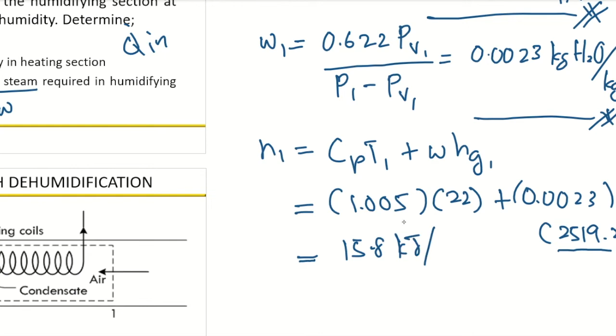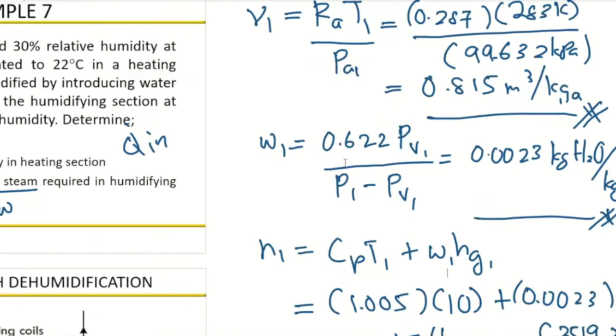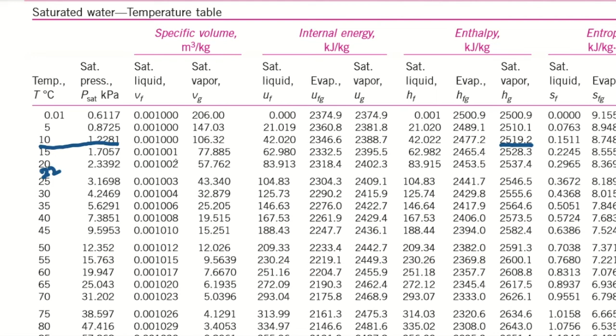So next we determine h2, which is Cp T2 plus omega 2 Hg2. Cp is 1.005 multiplied by temperature 2, which is 22. Omega 1 equals omega 2, because from state 1 to state 2 it's just a simple heating process, so omega is the same, 0.0023. Take a look at the property table at 22 degrees C. You need to find this Hg value by interpolation, and the value is actually 2541. So h2 is 28.0 kilojoule per kilogram dry air.